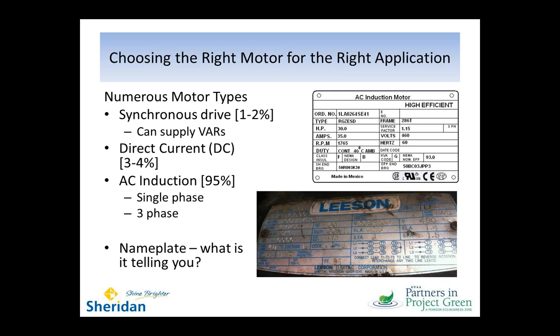You also see a very important number down in the bottom right, which is the NEMA nominal efficiency. That's telling you that this high efficiency motor is about 93% efficient. And it's important to pay attention to those numbers. As we'll see in a little while, efficiency can make a big difference in your cost.